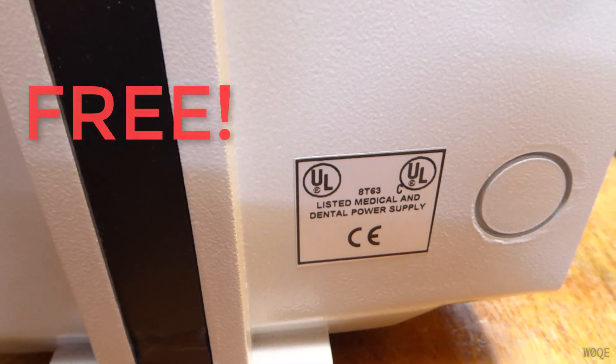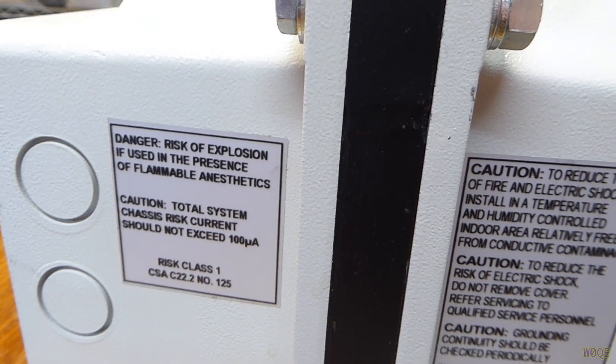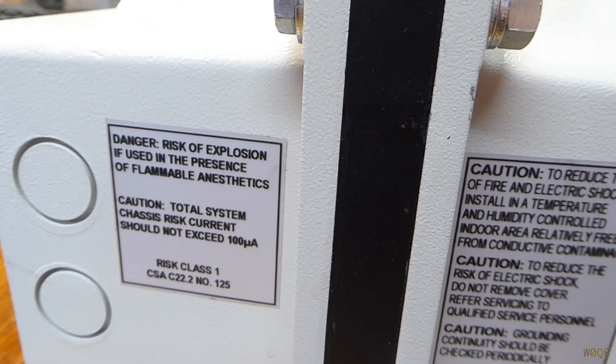The label indicates that this transformer was certified for medical and dental use. The output has two standard three-prong 120 volt outlets and I believe the leakage spec is 100 microamps maximum.